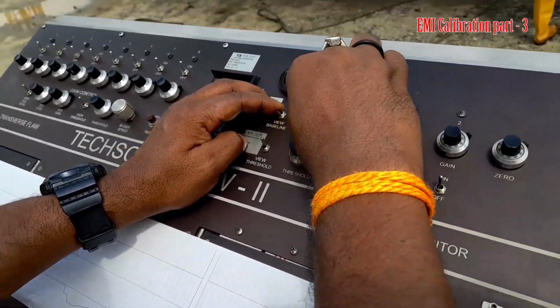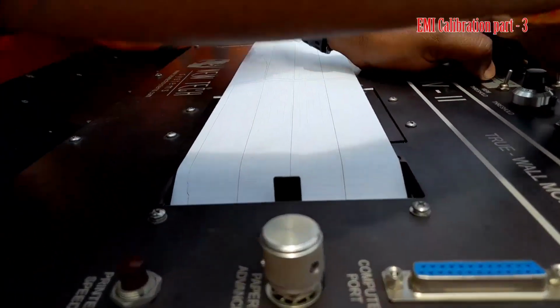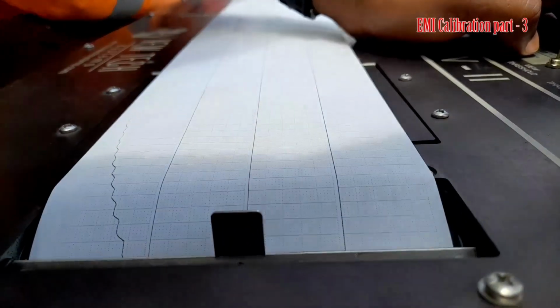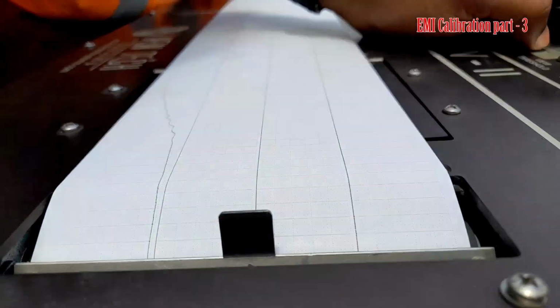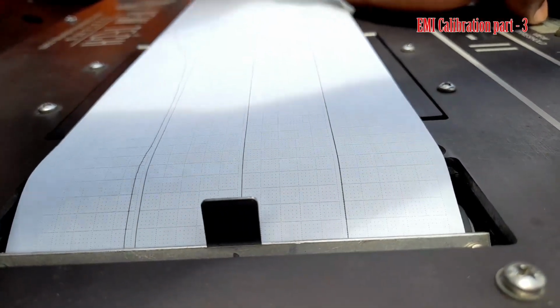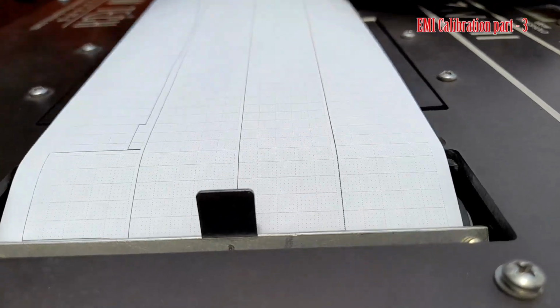Next is wall monitoring setup. There are also 3 methods. Before you start, check your baseline. Hold the baseline toggle switch and adjust the value to 1 mm, in between 1 to 5 mm. 1 mm is okay, you can get maximum accuracy. 1 mm or 2 mm from top. Always remember from top. All others we set up from bottom, but in this wall monitoring section the baseline is set up 1 or 2 mm from the top.